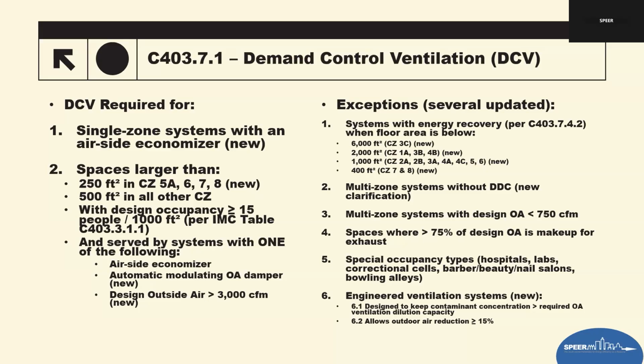And then space size thresholds are updated. So the second change basically is revising the 250 square foot threshold in colder climates, such as zones 5A, 6, 7, and 8. And then all other zones stay at 500 square feet. The DCV also applies only to spaces with 15 occupants or more per 1,000 square feet, consistent with the IMC. A new system types triggering the DCV, basically it adds 3 new triggers.